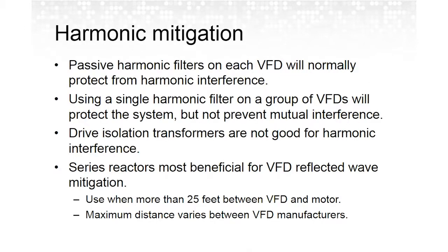So if we look at some methods for harmonic mitigation, one of the things I've used much of the time in the past is passive harmonic filters for each VFD. The problem with applying any kind of harmonic filter on a group of VFDs for a group of motors is that the VFDs can interact with each other. You may be able to mitigate the harmonics going back into the distribution system, but then the VFDs interact with each other. Drive isolation transformers are really good for isolating motors from VFDs to prevent the reflected wave issue. Or series reactors work well, but don't try to depend on drive isolation transformers to limit your harmonic interference.